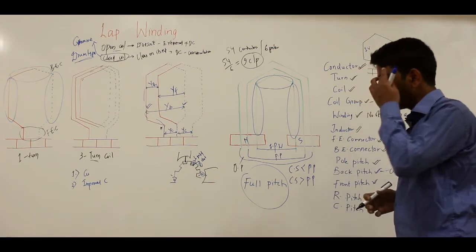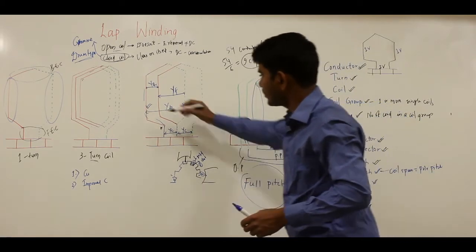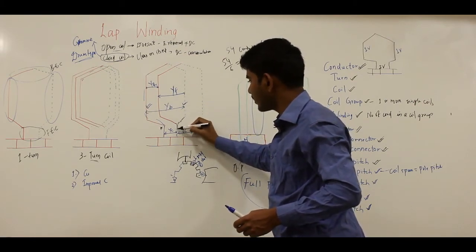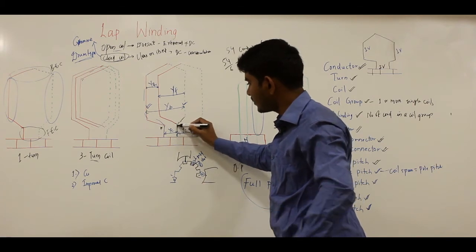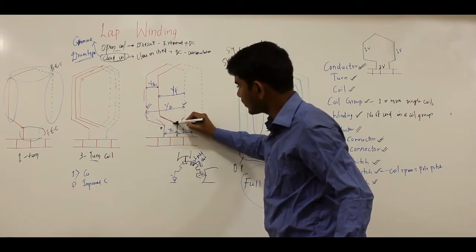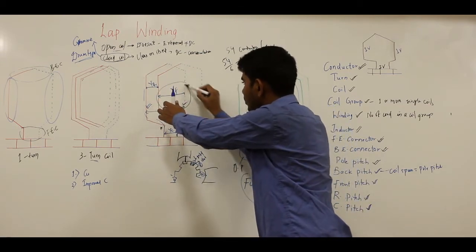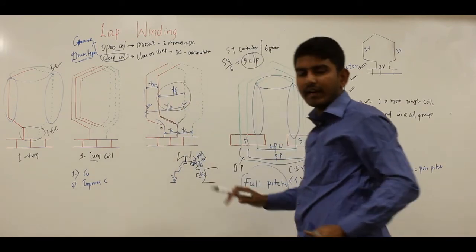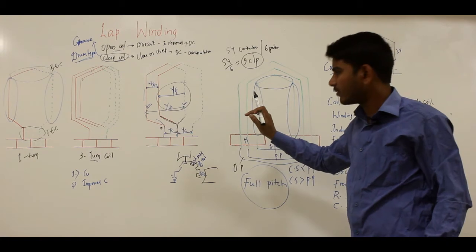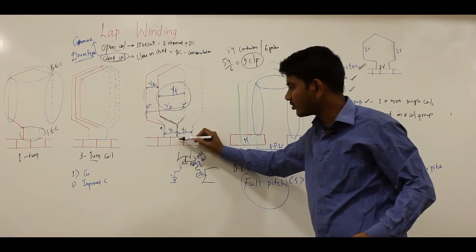In lap winding, the starting side and finishing side of a coil can be seen clearly. The finishing side of a coil is connected to a commutator segment, and this finishing side is also connected to the starting side of the next coil. There is an overlap between successive coils — this overlap is why this type of winding is referred to as lap winding. Simply defined: in lap winding, the finished side of one coil is connected to the starting side of the next coil as well as to the commutator segments.